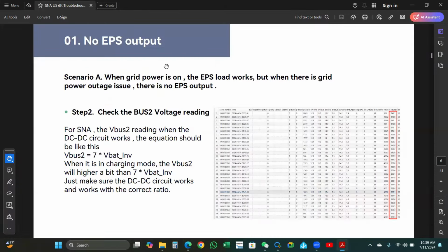And next one, no EPS output. Scenario A, when the grid power is on, the EPS load works, but when there is a grid power outage issue, there is no EPS output. Step two, check the bus two voltage reading. For SNA, when the DC to DC circuit works, the equation should be: Vbus2 equals 7 times VBAT_INV. When it is in charging mode, the Vbus2 will be a bit higher than 7 times VBAT_INV, just to make sure that the DC circuit works and works with the correct ratio.